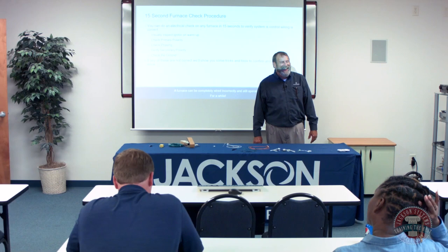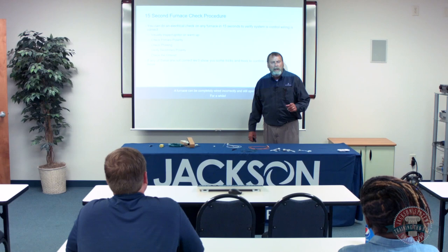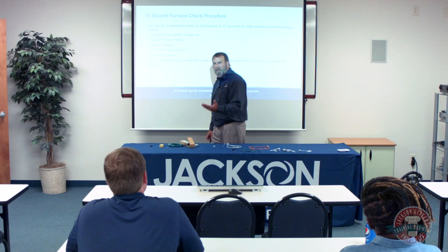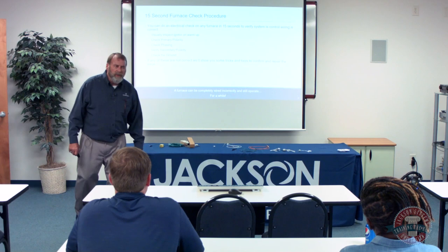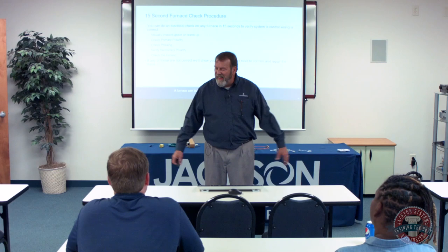Literally, guys, L1, chassis ground, L1, TH, measure the voltage, measure the polarity, measure the phasing. That is all there is to this trick. And as the igniter's starting to glow, look for the hot spot. You can eliminate a lot of issues with polarity, grounding, phasing, broken igniters, literally on the first startup when you're doing a clean and check.